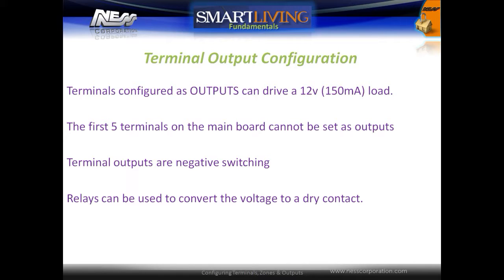Terminals configured as outputs can drive a 12-volt load up to a maximum of 150 milliamps. The first five terminals on the main board cannot be set as outputs. Terminal outputs use negative switching, and relays can be used to convert the voltage to a dry contact.